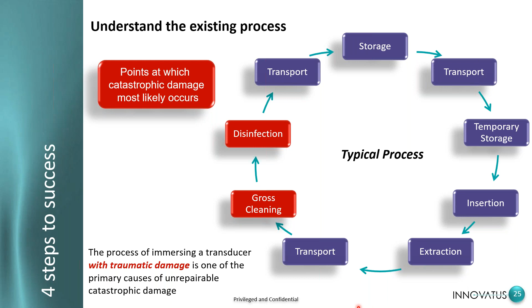Now, catastrophic damage. You see, we've moved over now. We're not talking about transport, storage, or even usage, where if somebody doesn't use a bite guard on insertion and extraction, that's a problem. They may nick the insertion tube. They may nick, not the bite guard, but the bending rubber. They may create a breach within that probe. That's a problem. But where the catastrophic damage occurs, where we really kill these probes, is during gross cleaning and disinfection. And that is the process of immersing a transducer with traumatic damage. So during these other stages, we've induced some type of trauma, some type of traumatic damage. But now we take it and we do gross cleaning and disinfection. That's where we take a damaged probe and we make the damage exponentially worse.